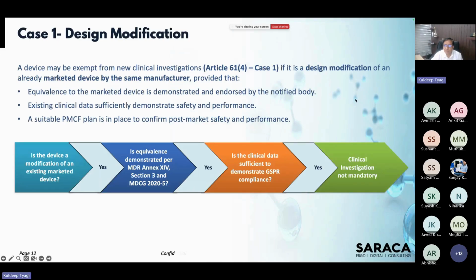So the first one is design modification, right? If you have to really do an assessment of this step by step, the first one is you will have to answer this question: is the device a modification of an existing marketed device, right? So it is. And again, as I said earlier, modification does not mean that you have changed a major feature or function of the device and you think you will get through it. Chances are very, very less. Make sure that you are not changing any of the claims substantially when you are making modifications. There are very minor modifications which you are doing, some enhancement there, right? That would be allowed. So if your answer is yes for this, then you go to the next one.